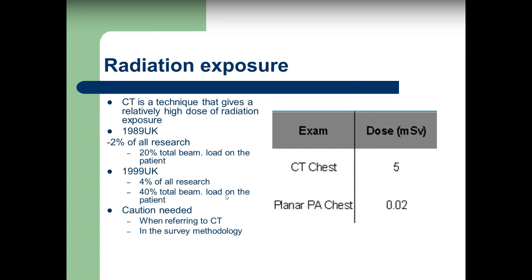making CT. Reducing radiation dose is desirable when possible, but it generally results in a decrease in image quality because of increased noise. CT radiation dose may be reduced to some degree by increasing gantry rotation time, pitch or slice thickness, by special scans, or by using other more complicated techniques, for example, artificial intelligence.